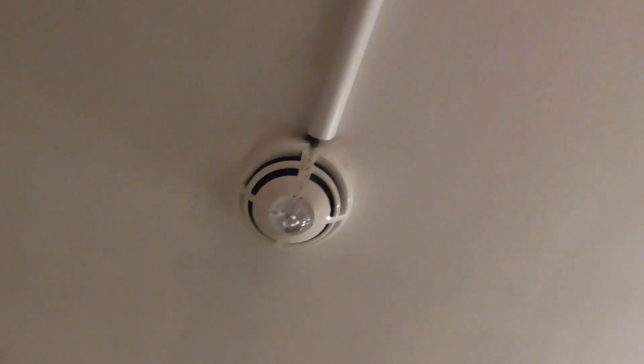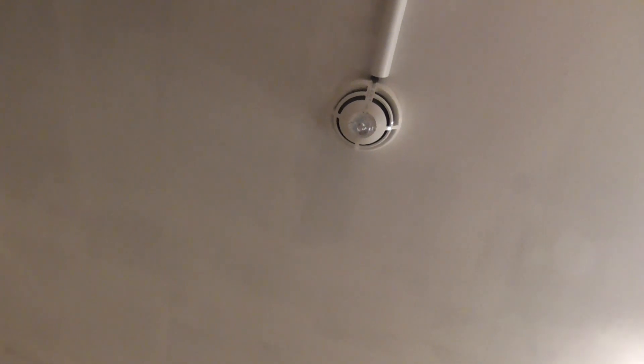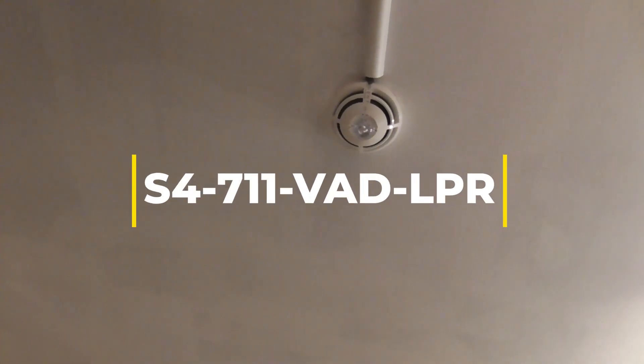So the first change we have is an S-Quad change. The 715 optical only detector has been taken down and been replaced with an S4-711, which is an optical heat sensor and VAD. As you can see, you can see the VAD there. That's the VAD S-Quad, that's the new device. I'm not sure if it's the LPR version or the HPR version, but I'll put the model numbers on the screen for you.